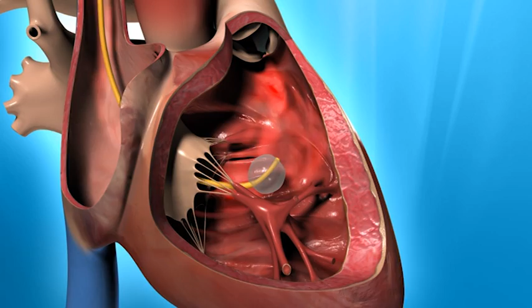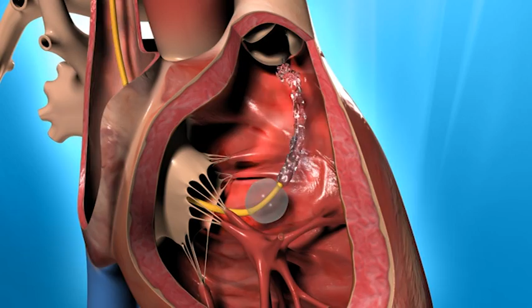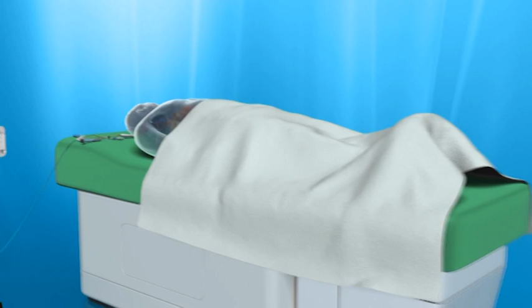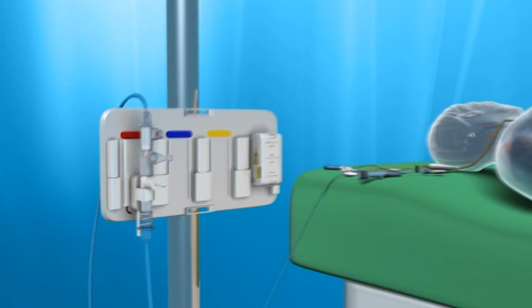Before each measurement, the RHC has to be flushed with physiological saline solution to avoid clotting in the catheter lumen and to ensure correct pressure readings. Also, before each measurement, the correct position of the transducer system should be checked again and the transducer zeroed by opening the stopcock.